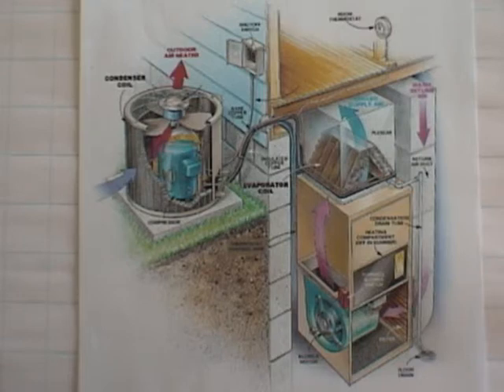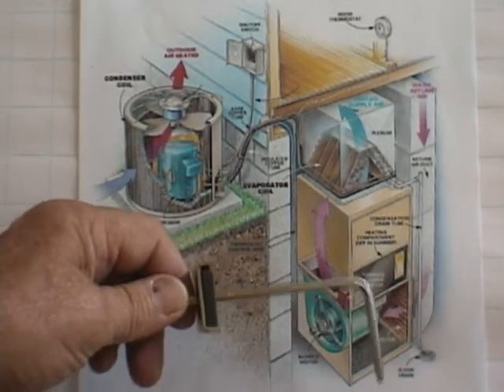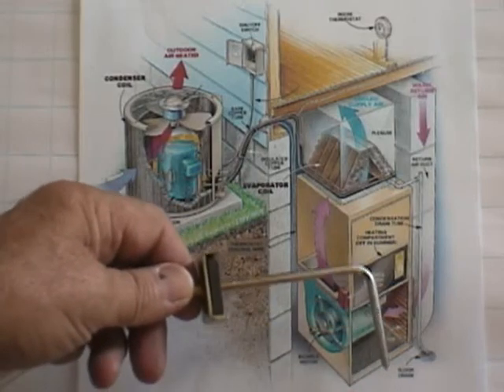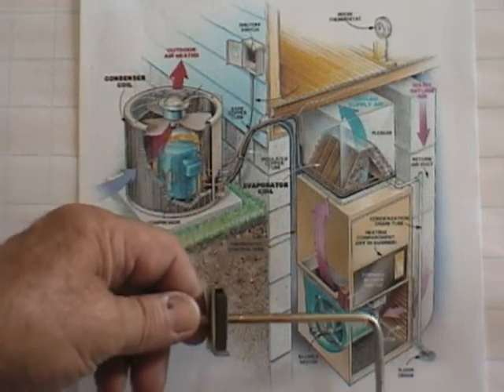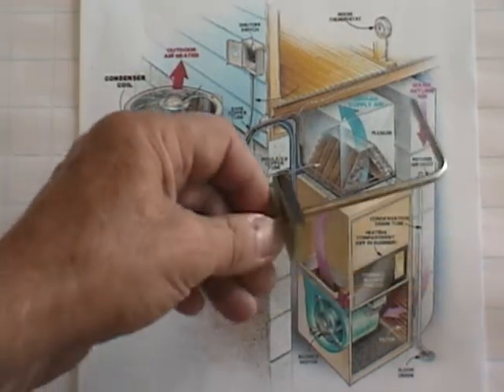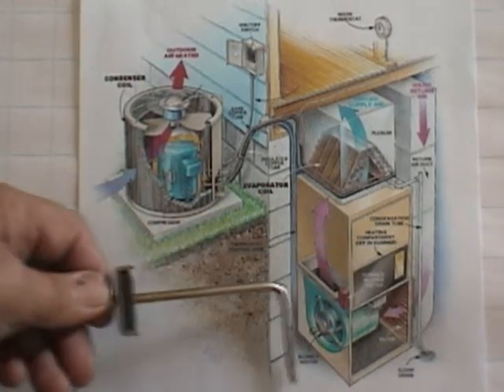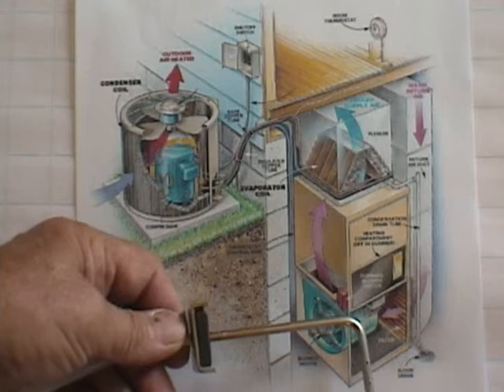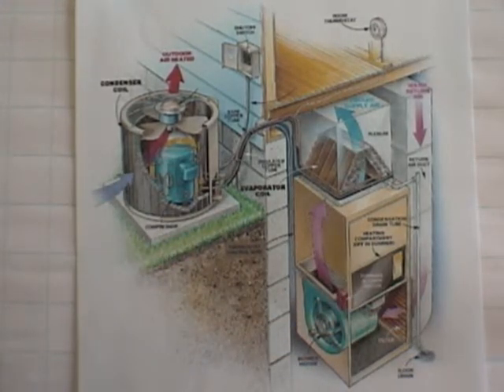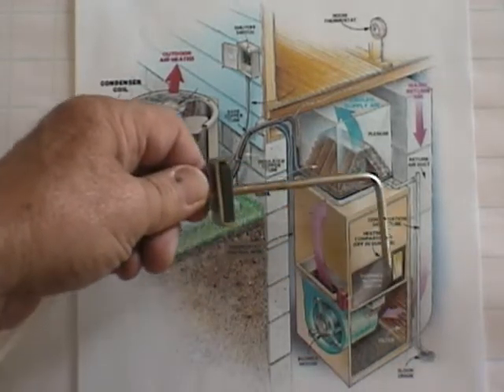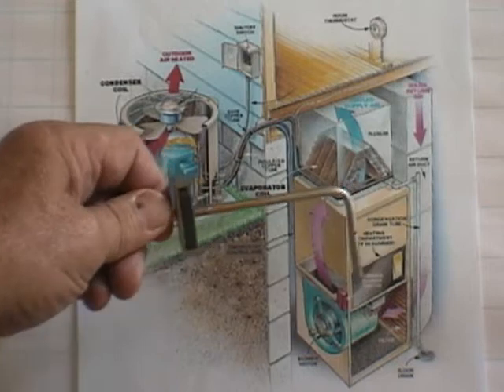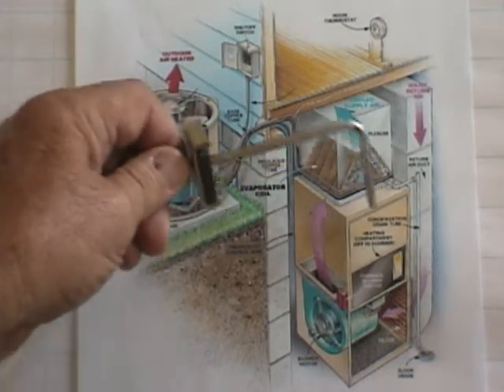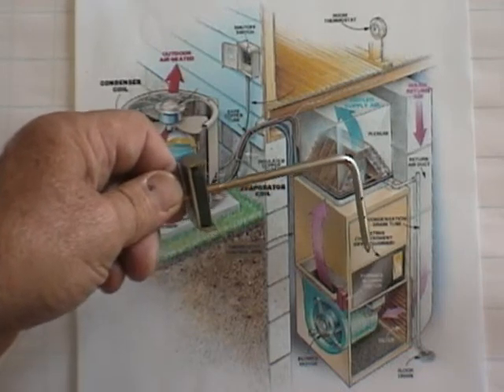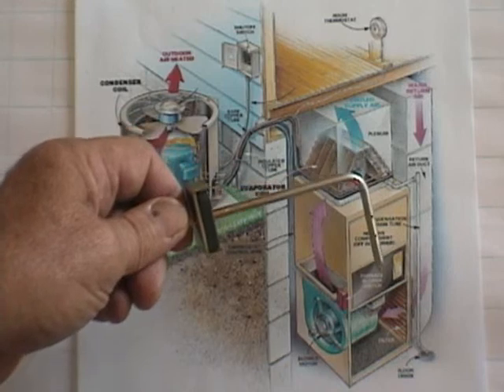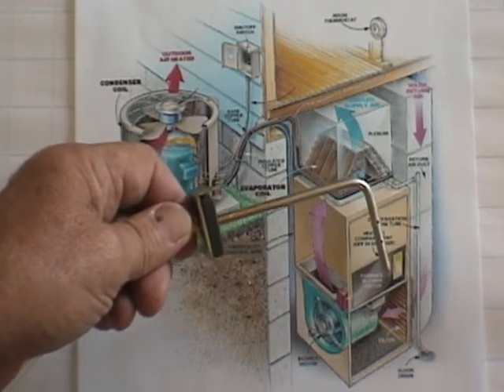If we want to measure total external static pressure for this furnace as an example, we would place one of the probes into the airstream on the suction side of the fan section. We could also place it in the return duct facing the airstream, of course. This airstream's coming up going this way, so we would place this probe in the side of this unit here, and that would give us our negative pressure. To check the other side of the unit, if we're just checking this furnace, then we would want to insert the second probe, the positive side, on the discharge after the heat exchanger in the furnace, but before the coil, and that will give us total external static pressure that will tie into the fan curves or airflow charts for this furnace.